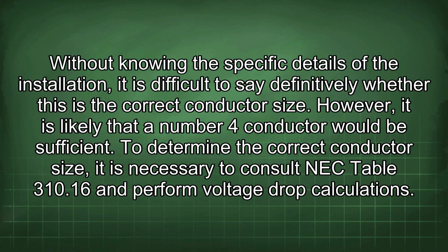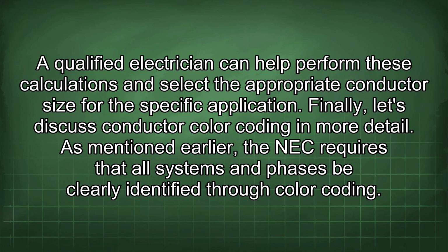However, it is likely that a number 4 conductor would be sufficient. To determine the correct conductor size, it is necessary to consult NEC Table 310.16 and perform voltage drop calculations. A qualified electrician can help perform these calculations and select the appropriate conductor size for the specific application.